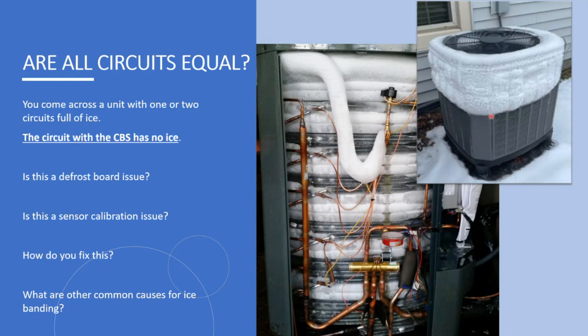So in this case, you would probably want to be checking the temperature of each of these separately, and each of the distributor pipes separately. And if you have a big delta between any of your coil circuits, say more than 10 degrees Fahrenheit, then you have unequal coil circuits. And you could move this sensor to the coldest circuit, and that may fix it. If that doesn't fix it, you may have to look at changing the outdoor coil to fix the defrost issue. Usually moving the sensor to the coldest circuit is going to do the trick.